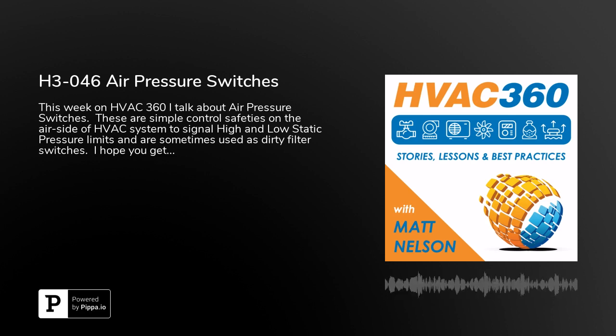So now that you've got the pressure class rating and you know what that is designed for, you want to set the limit to less than that, just slightly less than that. You don't want to exceed it. Meeting it is probably a bad idea too. Basically, if you meet or exceed the pressure class rating, there's a good chance that you're going to end up blowing out the ductwork. It's either going to explode or it's going to implode.